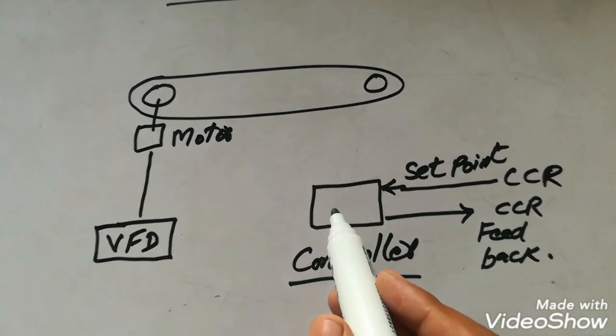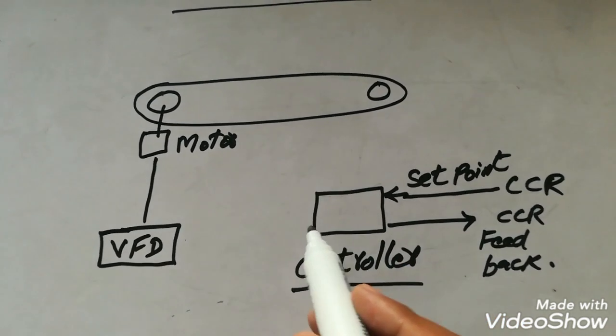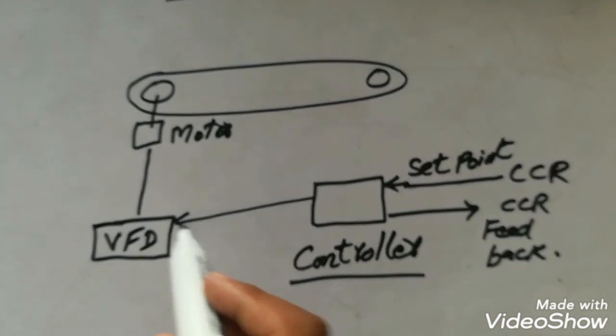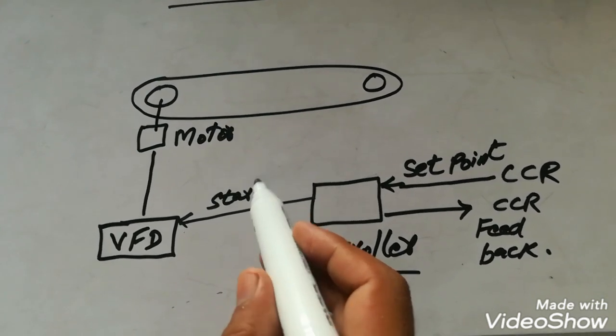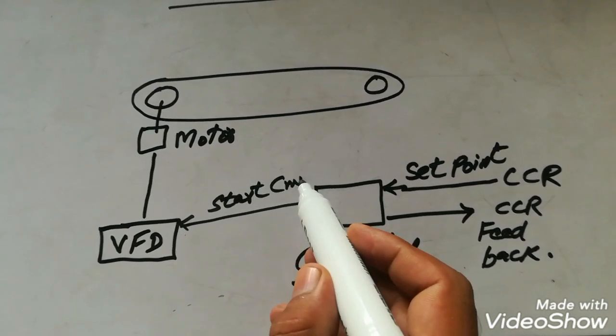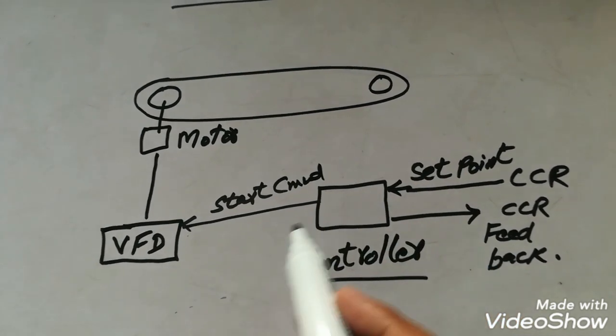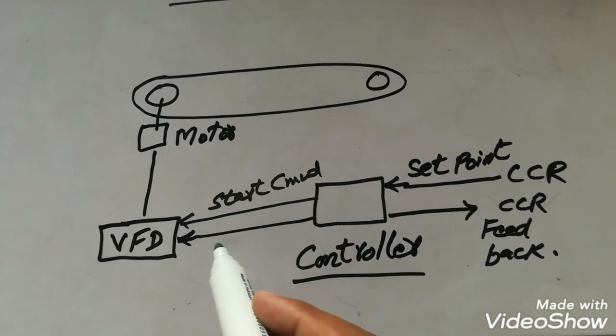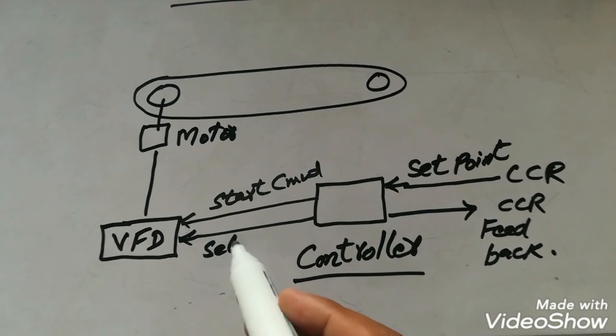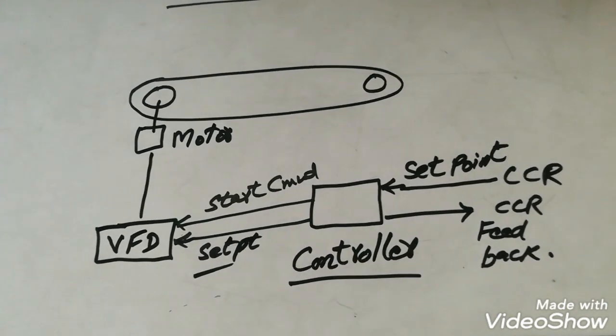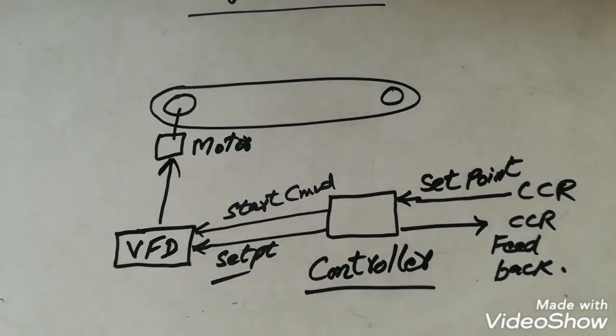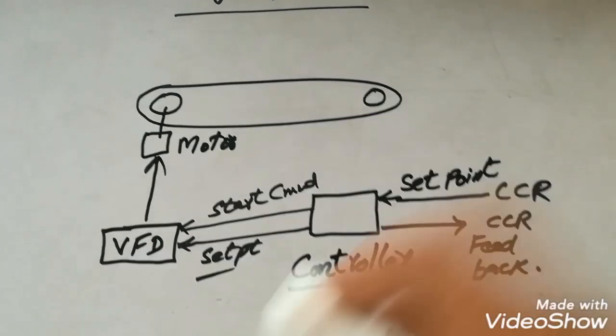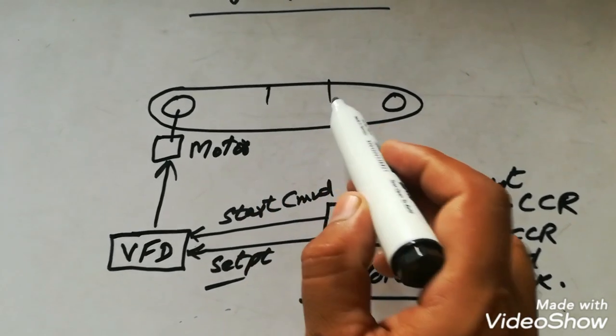If operator gives the set point to the controller, controller will give a start command which is a digital output and digital input of the VFD. It will start the VFD and also give an analog signal to the VFD which is 4 to 20 mA. It will control the speed of motor so motor will start running.